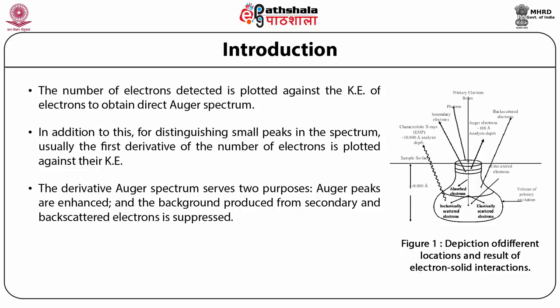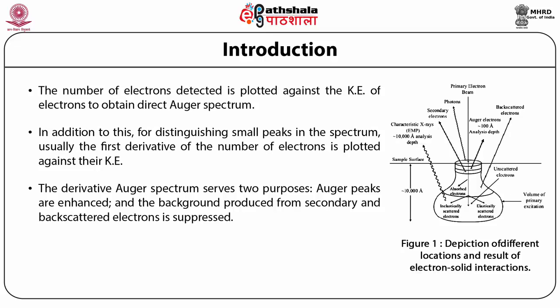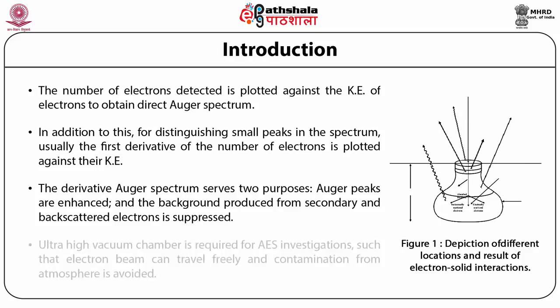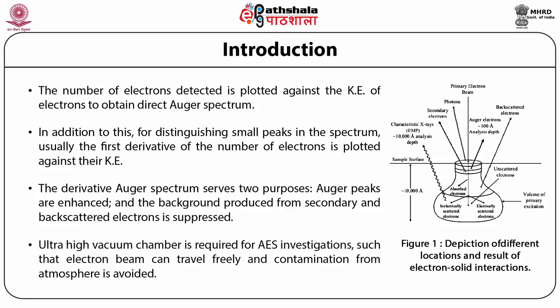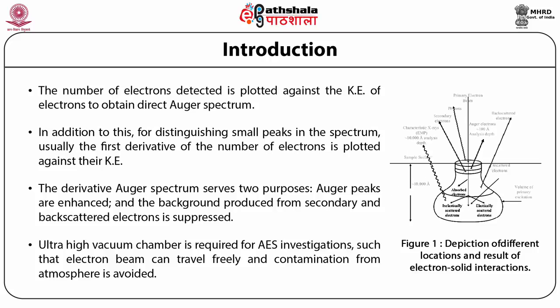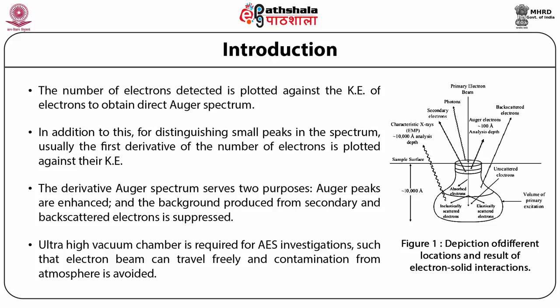The derivative Auger spectrum serves two purposes: Auger peaks are enhanced and the background produced from secondary backscattering electrons is suppressed. An ultra-high vacuum chamber is required for AES investigations so that the electron beam can travel freely and contamination from the atmosphere is avoided.